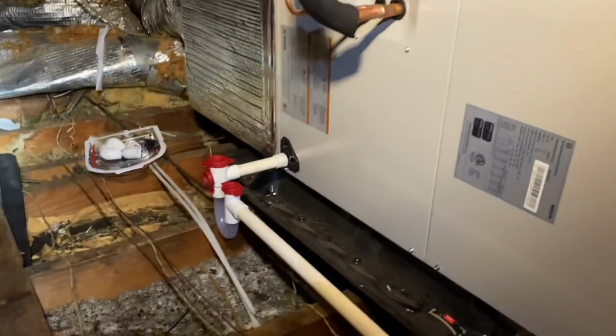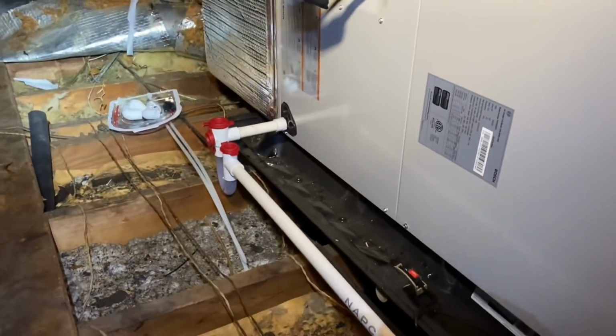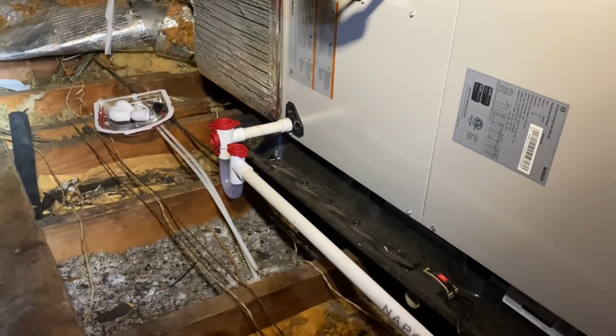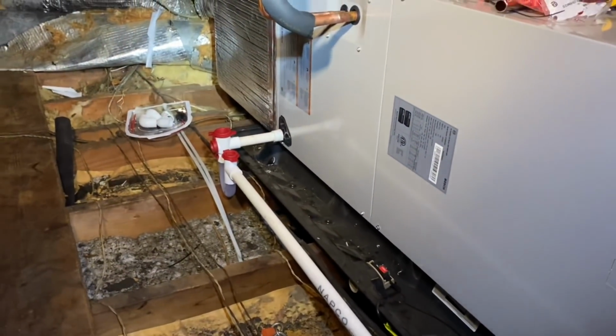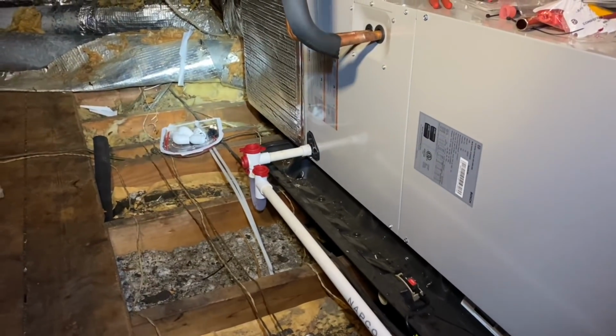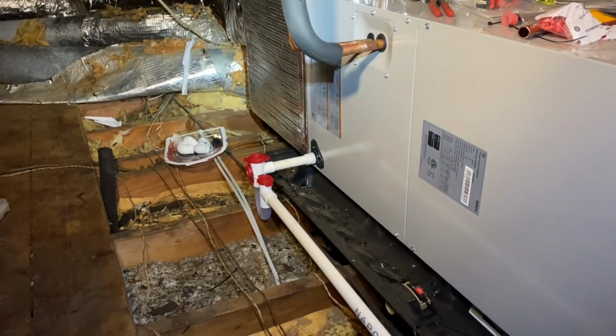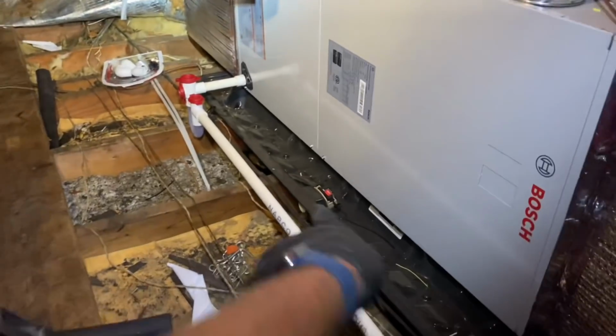There's the clear condensate trap. I also have to wrap that with some insulation. I've got a piece right there, because in an unconditioned space, that clear trap needs to be insulated. I learned that a few months ago, guys. Thanks for pointing that out to me. It's written on the labeling. We're going to run the emergency drain out from there.